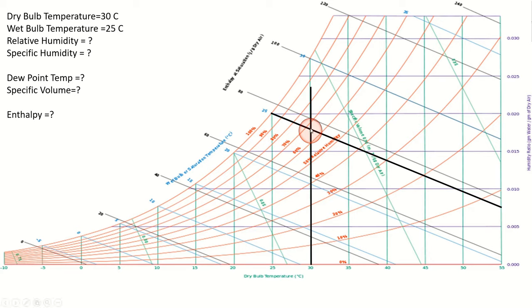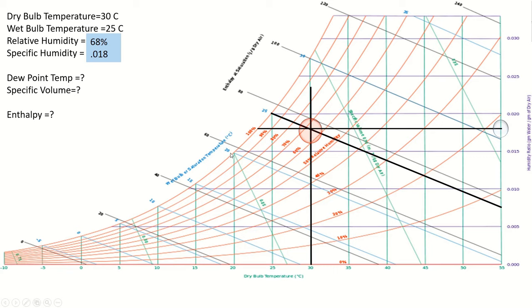For relative humidity: the intersection point falls between the 60% and 70% humidity lines, nearest to 70%, so relative humidity is around 68%. For specific humidity: drawing a horizontal line to the humidity ratio scale, the value is between 0.015 and 0.020, nearest to 0.020, so specific humidity is approximately 0.018. For dew point temperature: drawing a horizontal line from the intersection point to the saturation curve, the value is between 20 and 25, approximately 23.5°C.